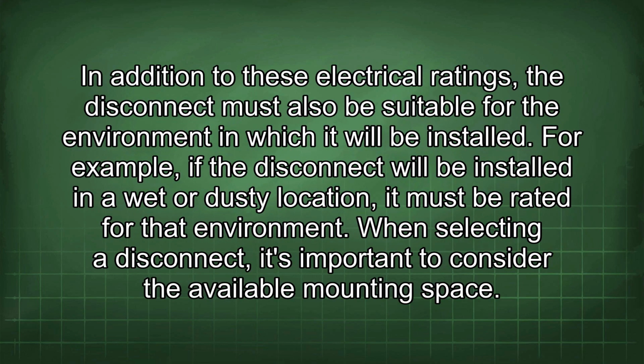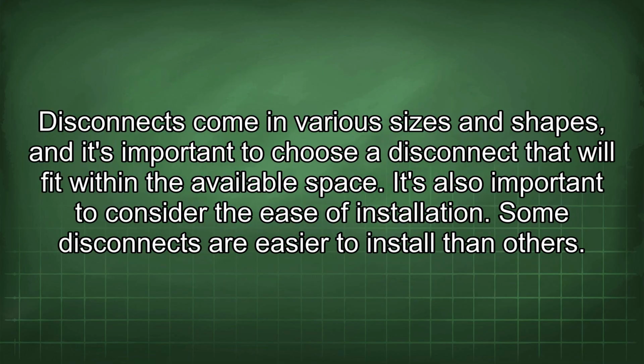In addition to these electrical ratings, a disconnect must also be suitable for the environment in which it will be installed. For example, if the disconnect will be installed in a wet or dusty location, it must be rated for that environment. When selecting a disconnect, it's important to consider the available mounting space. Disconnects come in various sizes and shapes, and it's important to choose a disconnect that will fit within the available space. It's also important to consider the ease of installation. Some disconnects are easier to install than others.